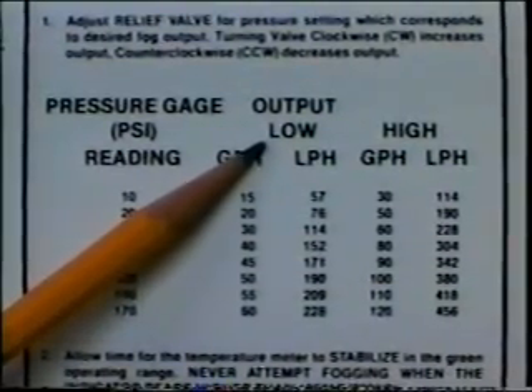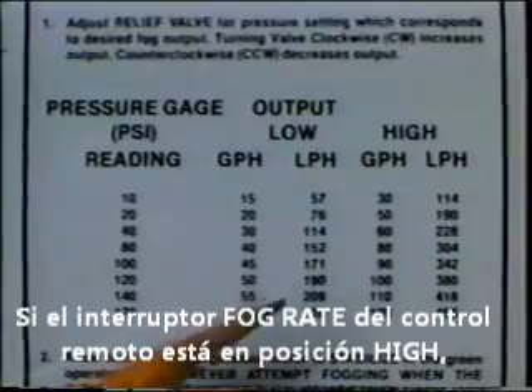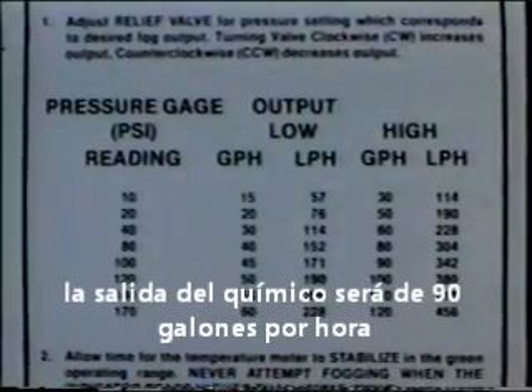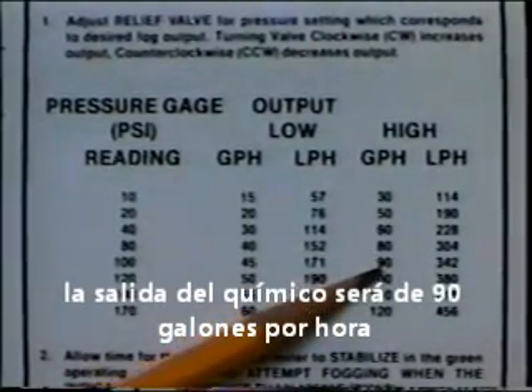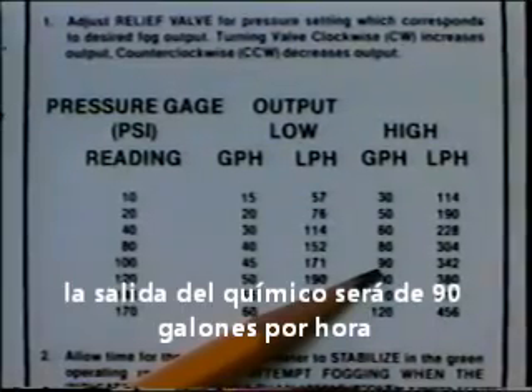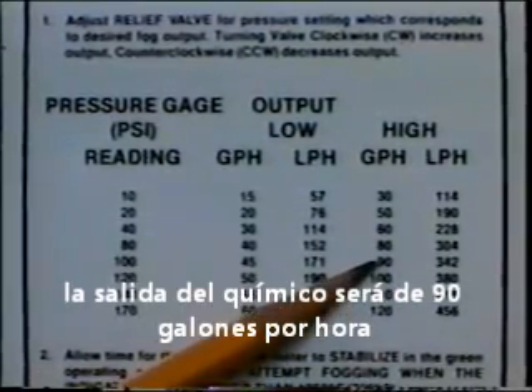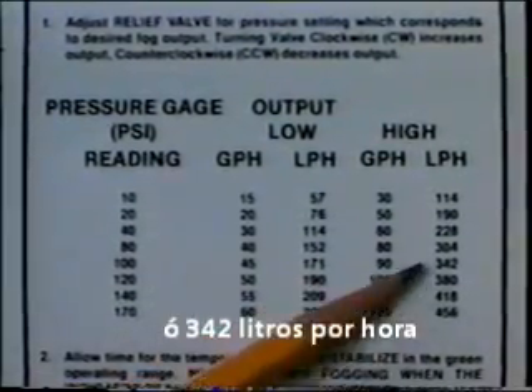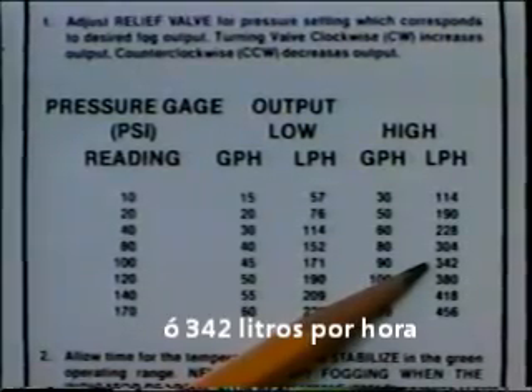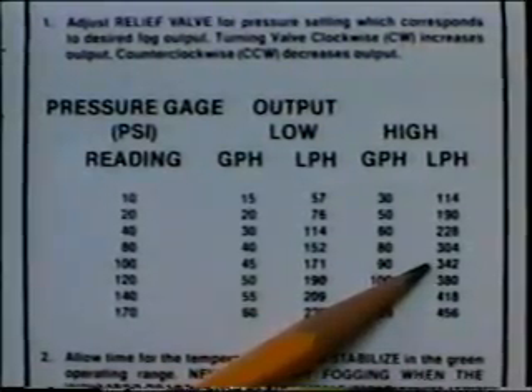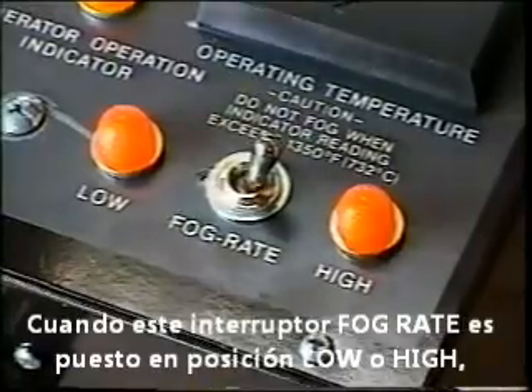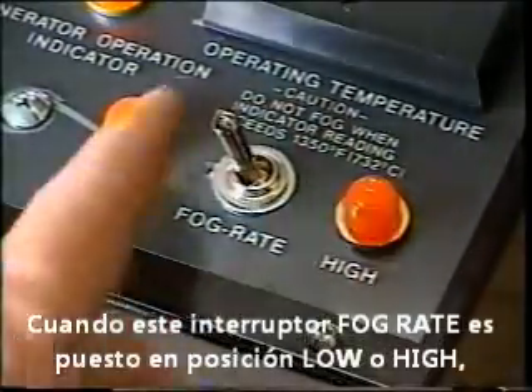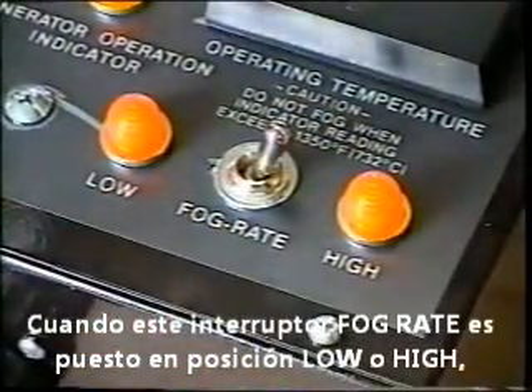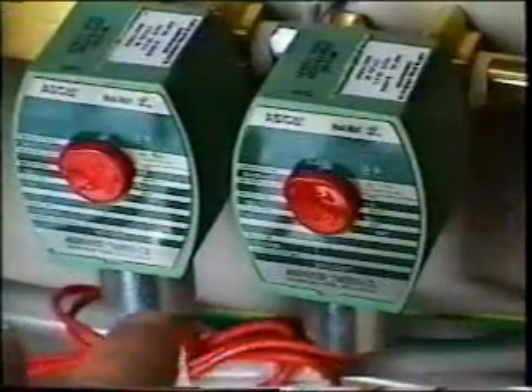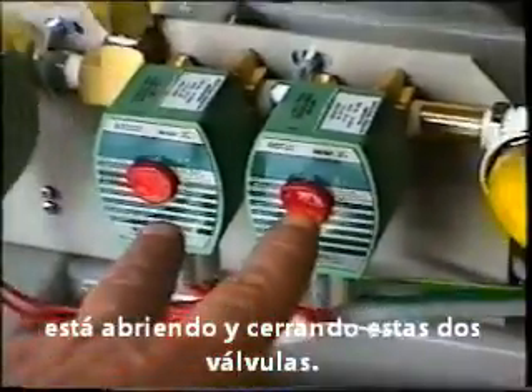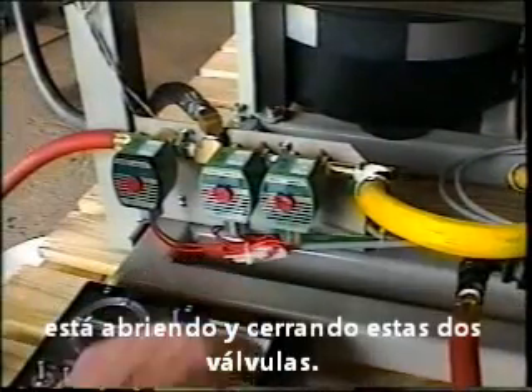If the fog rate switch on the remote control box is put into the high position, the chemical output would be 90 gallons per hour or 342 liters per hour. When this fog rate switch is put in the low or the high position, it is opening and closing these 2 valves.